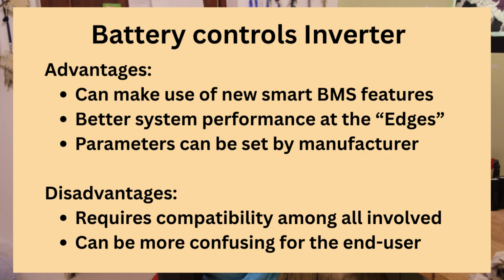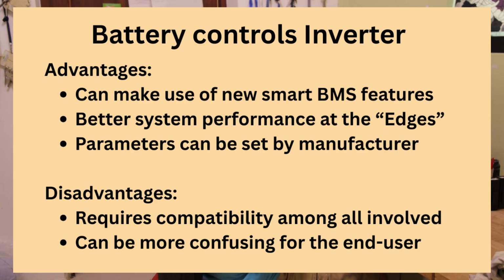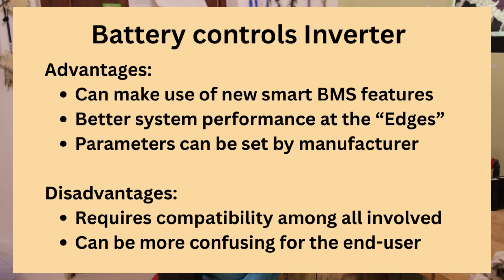The second advantage is that you can have a better system performance at the edges. So when in the other method the inverter would reach a constant voltage phase, this will start reducing your output current or input current, while when the inverter is controlled by the BMS, this will be just like clear cutoffs, right? So you will run into that limit and bang, the BMS will just cut out. So there's no transition phase there at the edges. Then parameters can also be set by the manufacturers. So if they get it right, the user might not have to set anything in the BMS anymore or at the inverter, because BMS and inverter are exchanging the information and setting it there.